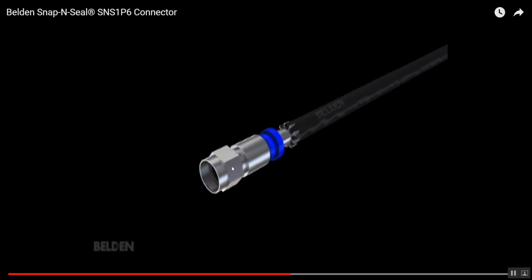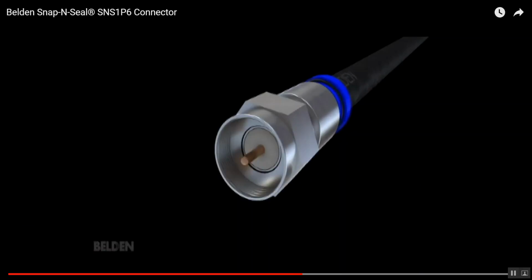That compression connector is going to slide on. This is actually going to make the compression and the securing of the connector onto the cable. As we slide that all the way up, I'm stopping again. This is your dielectric, okay? This should be flush with that inner metal ring inside the connector. That gives it the proper length, all right?